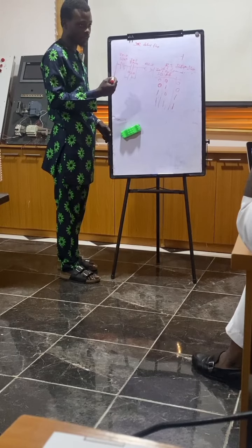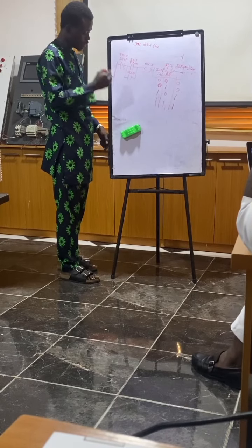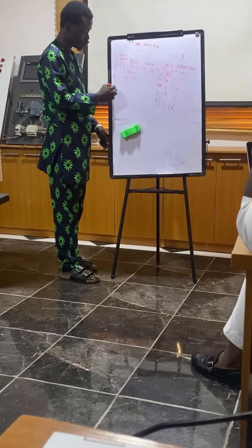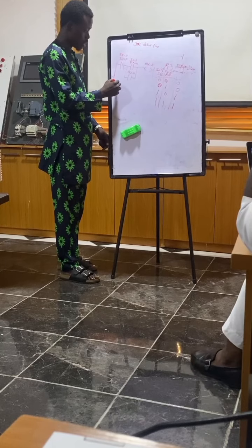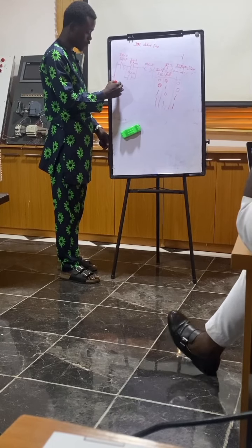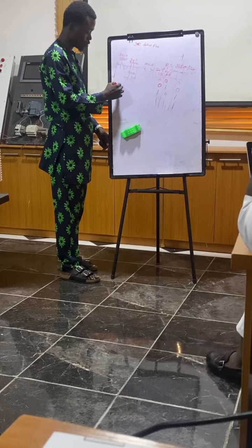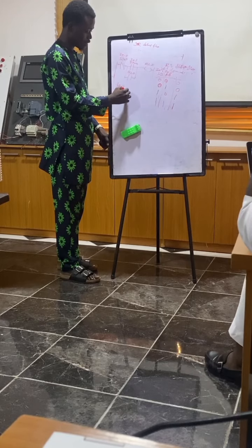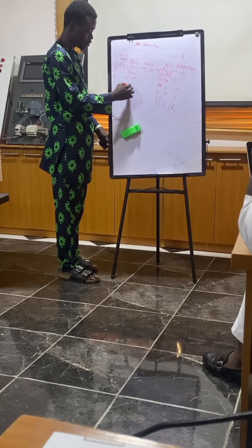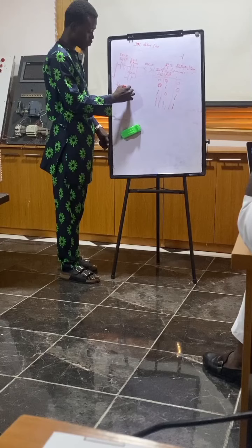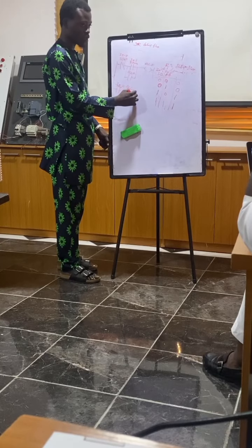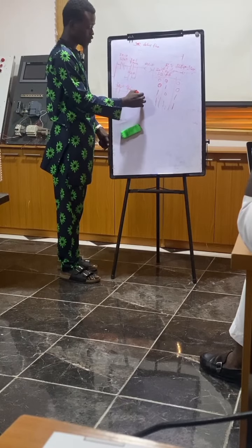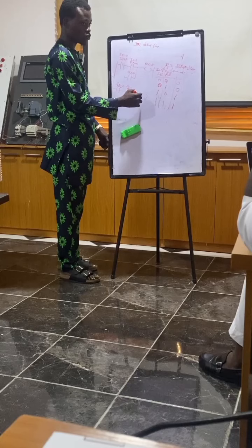What's the condition for RS? The condition for RS is such that when the two buttons, I0.0, that is the stop, and the I0.1, the start, when they are pressed, okay, we still want the set to dominate.